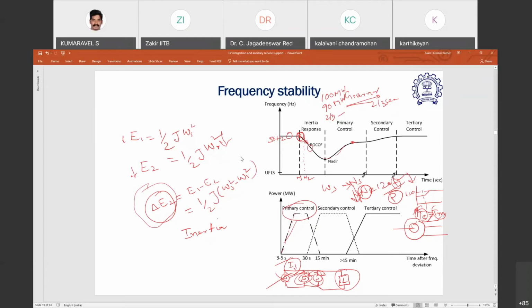Then only, as I was mentioning, it is 90 megawatt. If it is operating at 100 megawatt, it cannot release the power. It doesn't have the margin. It doesn't have the available power with it. So that available power is known as reserve. In addition to the normal power dispatch, the available power is known as reserve. For primary frequency control, we need primary frequency reserve.